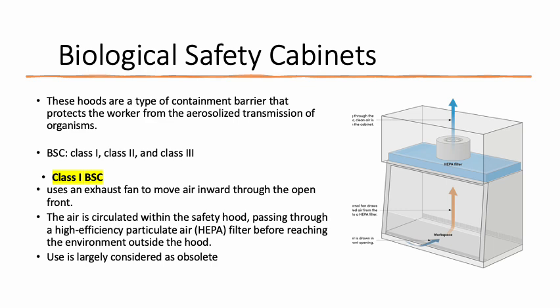Ang kinaibahan lang po ng class 1 to other classes of biosafety cabinet is that, as you can see here, the air po that is supplied inside the biosafety cabinet is not filtered by the HEPA filter. Isa lang po yung filtered po niya at ang pinefilter lang po niya is the air going outside. No? Kasi nga po, the air should be decontaminated by filtering system po using a HEPA filter. Okay? So usually class 1 BSC is now obsolete.